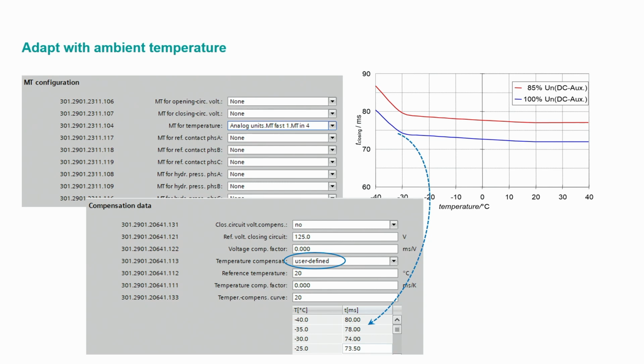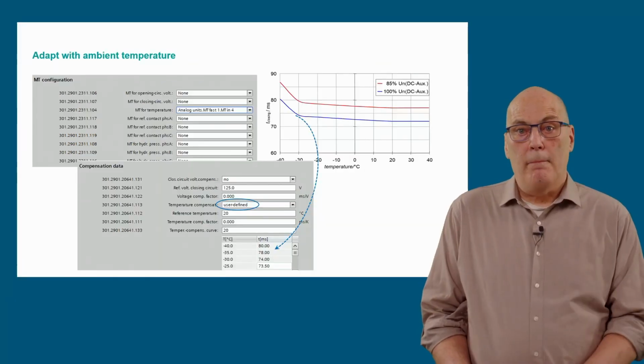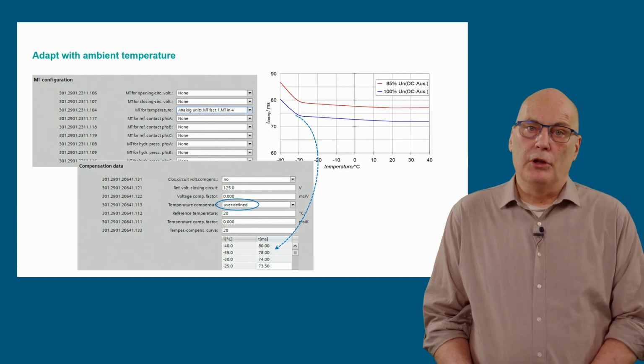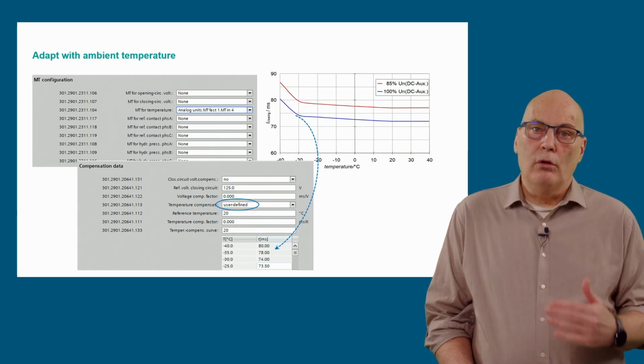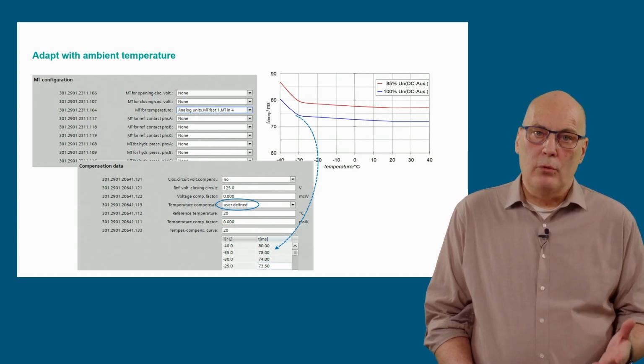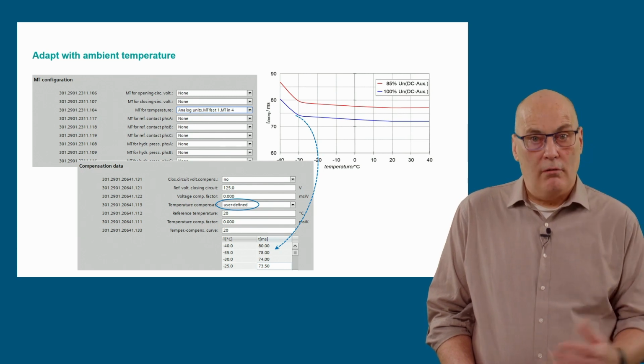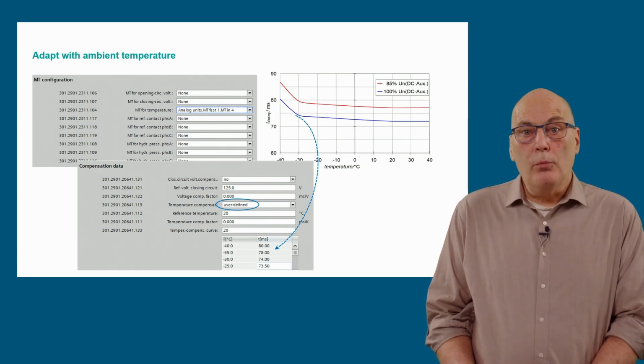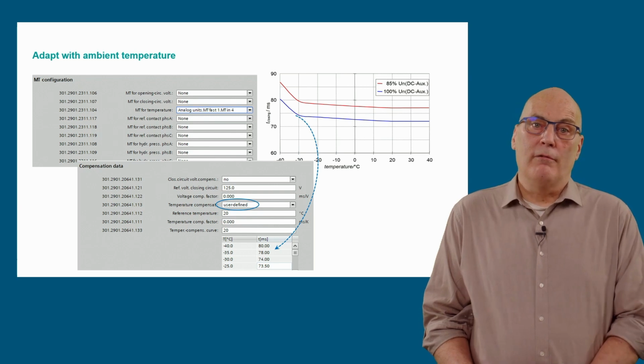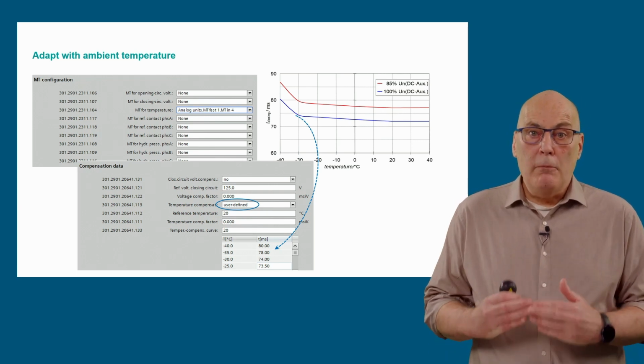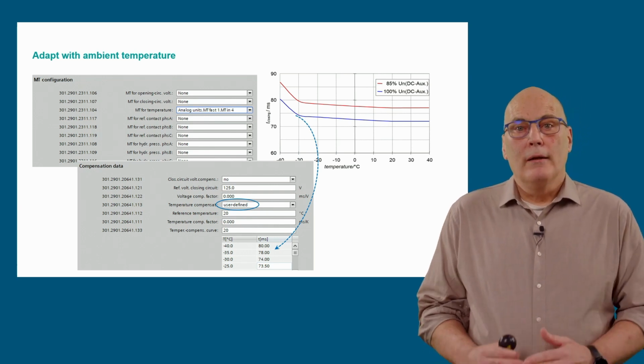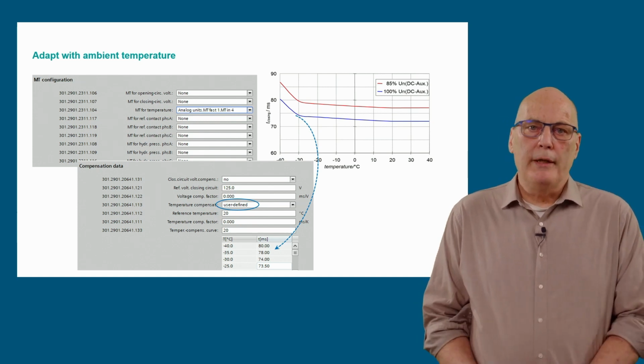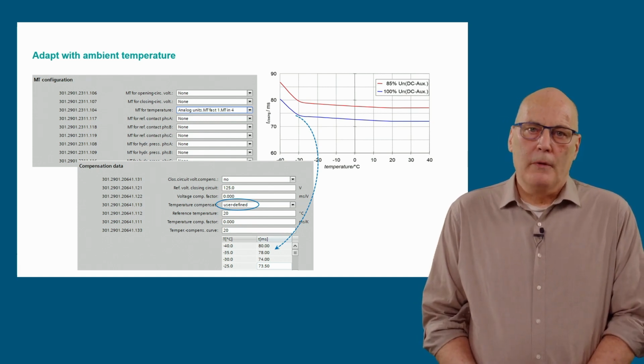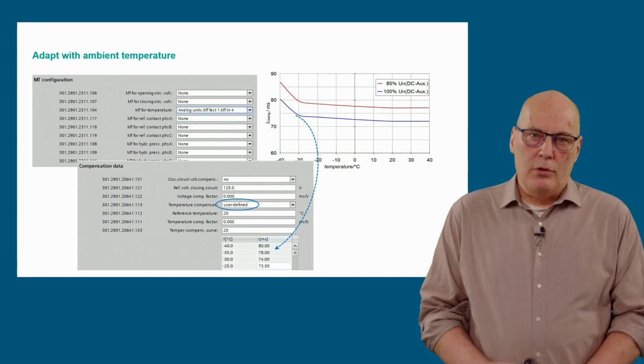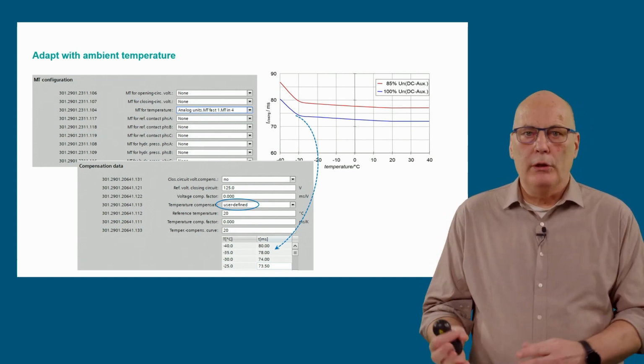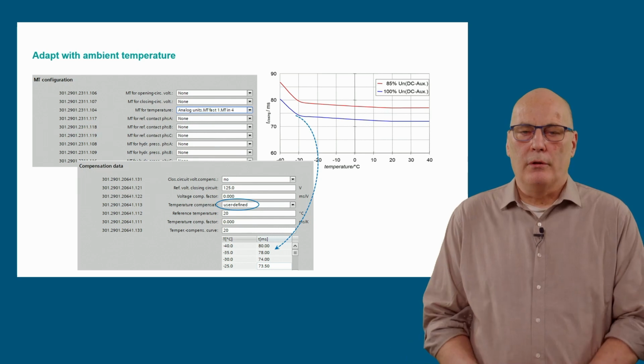Note that the curve shows two influences on closing time: temperature and control voltage. In this case, control voltage has a linear influence between 85 and 100% of nominal voltage. This will be considered separately in the following slide. For the temperature compensation, it is assumed to be at nominal voltage, over the indicated horizontal temperature range from minus 40 degrees C to plus 40 degrees C.